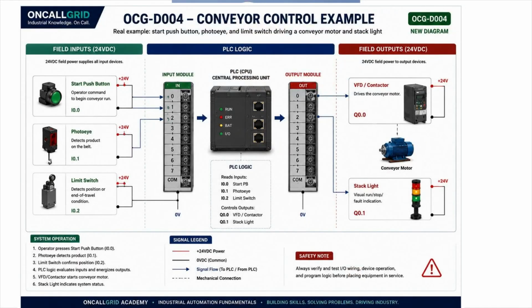And here's something worth keeping in mind for each one. What does it typically look like when it fails? A push button wears out at the contacts. A photo eye picks up a dirty lens or drifts out of alignment. A proximity sensor's sensing distance can drift over time.